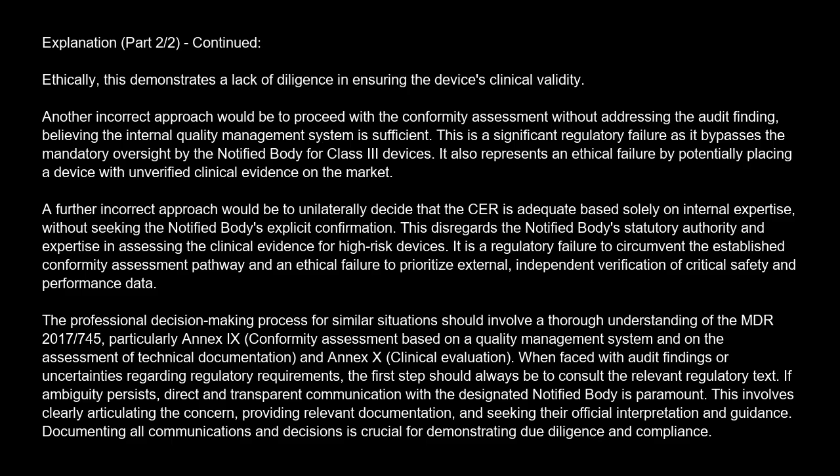The professional decision-making process for similar situations should involve a thorough understanding of the MDR 2017/745, particularly Annex IX, conformity assessment based on a quality management system, and on the assessment of technical documentation, and Annex XIV, clinical evaluation.